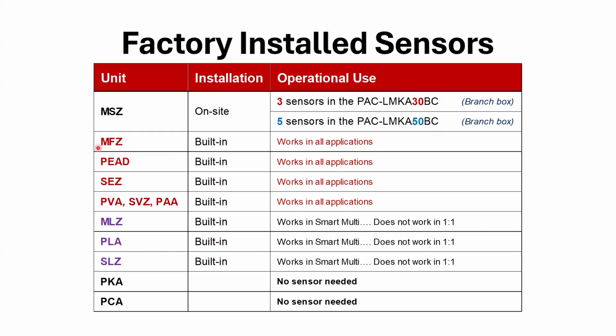If you have these units here in red, MFZ, PEAD, SEZ, PVA, SVZ, PAA coil, the sensor is built in and works in all applications on those. Your MLZ, PLA, SLZ right here, built in, so it works in the smart multi and it does not work in the one-to-one. Again, the outdoor unit is determining if it's going to look at that sensor and use it or not. No sensor needed on those particular units there. Yeah, A2L red color is for the refrigerant sensor used for all the installs.